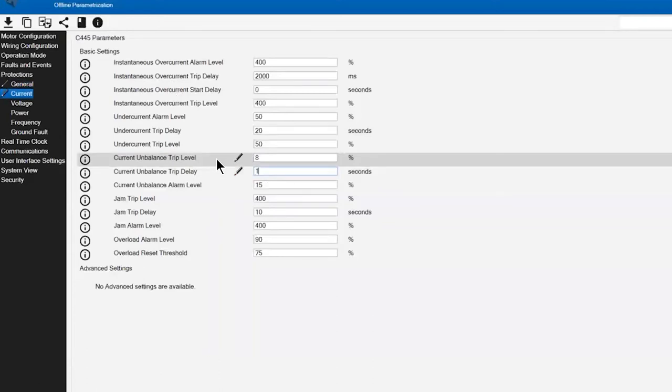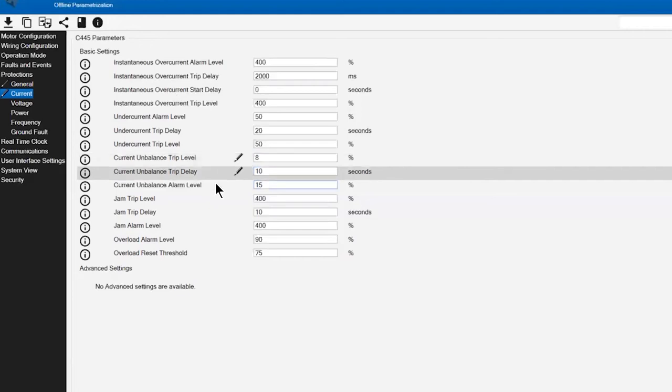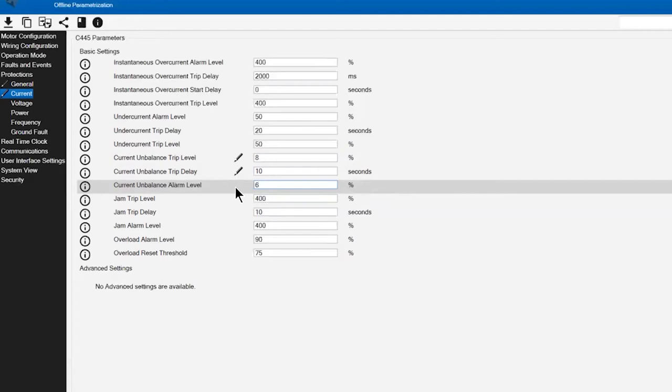The trip delay is appropriate anywhere from 10 to 15 seconds just to handle fluctuations within the power distribution system. I'm also going to configure an early warning alarm associated with that condition at a lower percentage value of 6%. This gives me that early warning view or alarm.